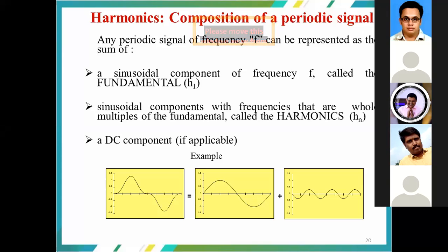So, for example, the third order harmonic has 150 hertz, and the fifth order harmonic has 250 hertz. That is the thing which is going to affect the operation of all components from the distribution side to the larger power grid networks. If there are DC components, the DC components get nullified. The even order harmonics get nullified due to the Fourier series effect.